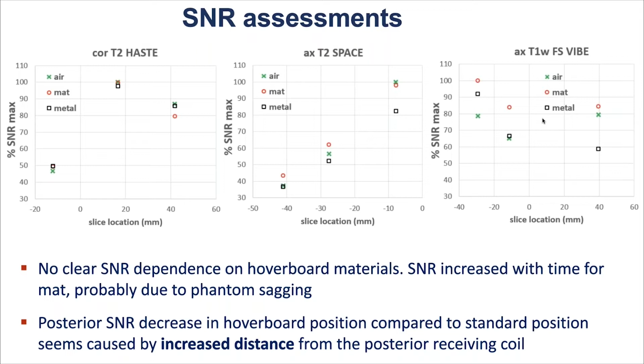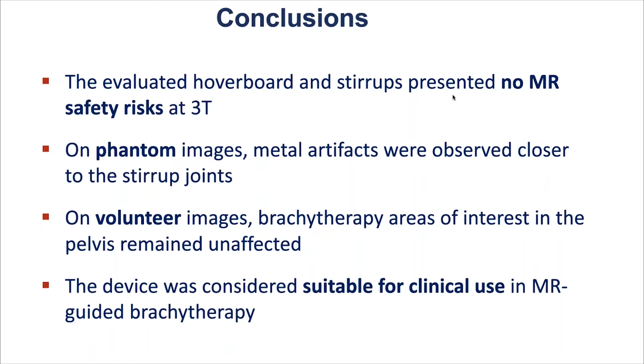To conclude, the evaluated hoverboard and stirrups presented no MR safety risks at 3 Tesla. On phantom images, metal artifacts were observed close to the stirrup joints, but on the volunteer images, the artifacts were affecting only hip areas, and brachytherapy areas of interest in the pelvis were not affected. Overall, image quality was considered suitable for the treatment planning, and as the device presented no risks, it was considered suitable for clinical use in MR-guided brachytherapy.